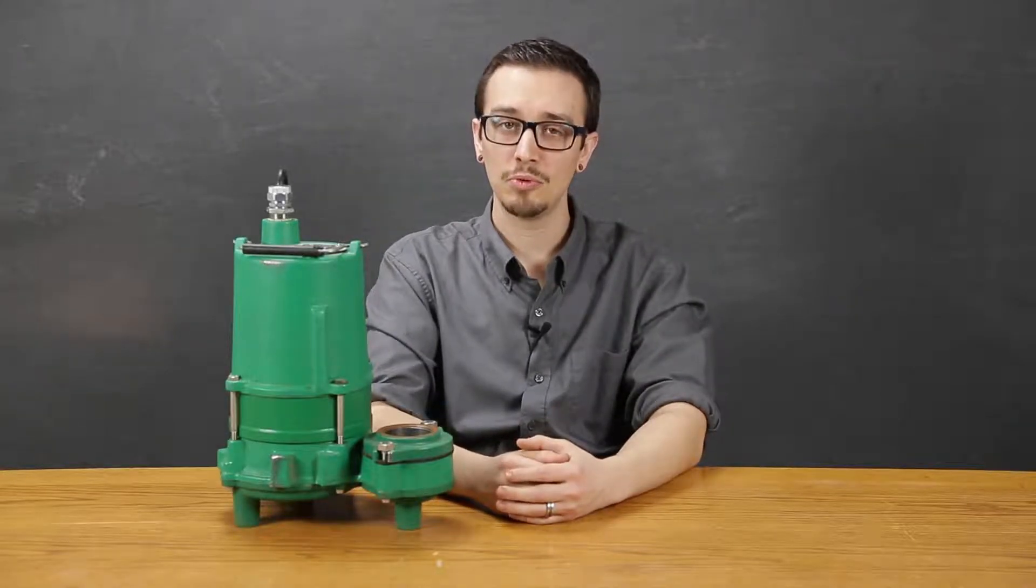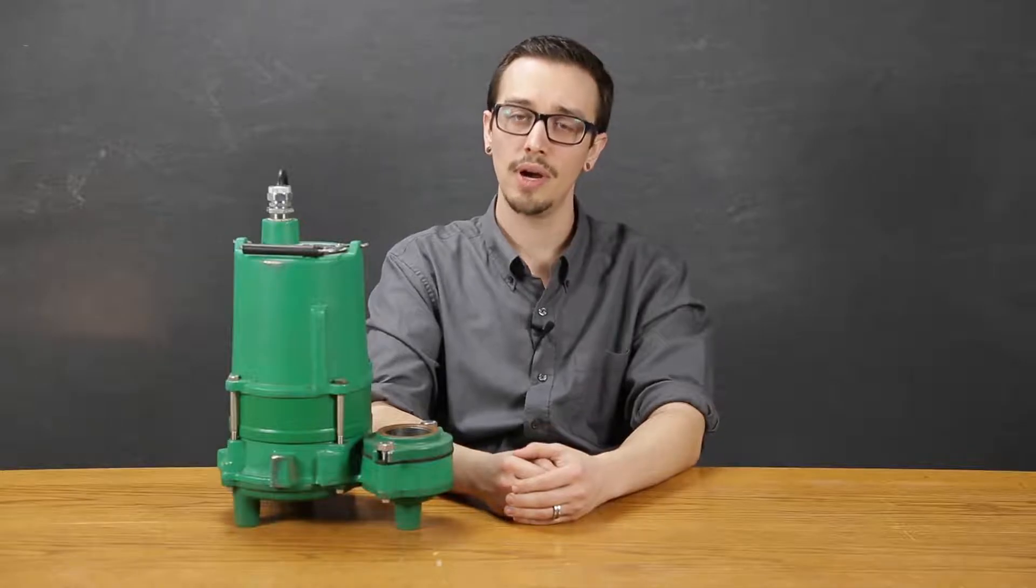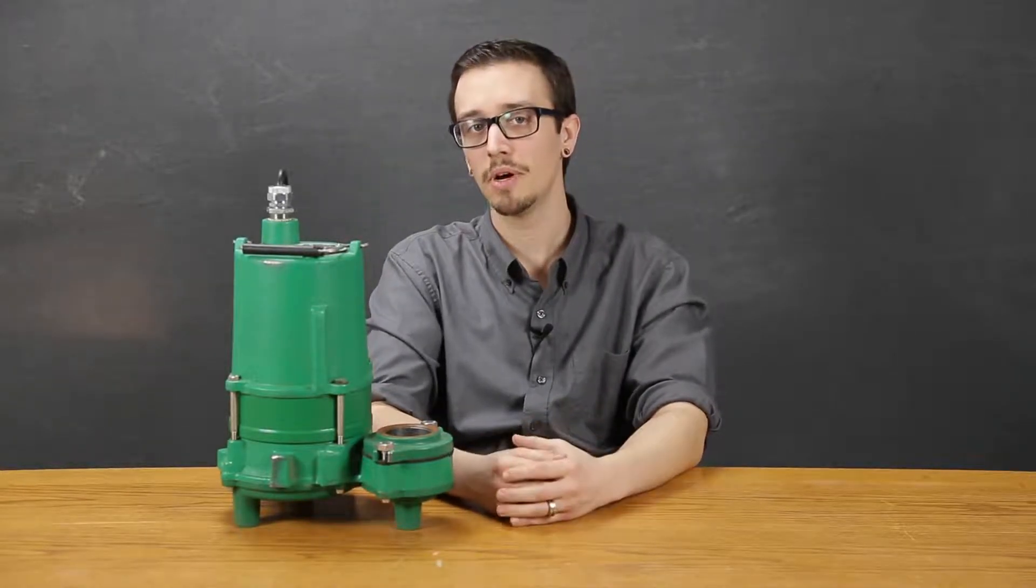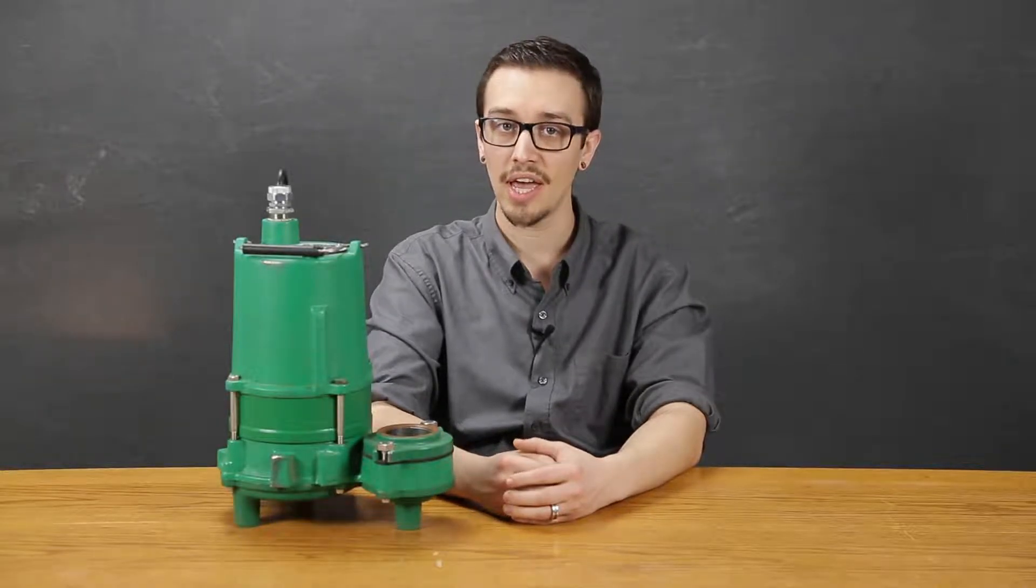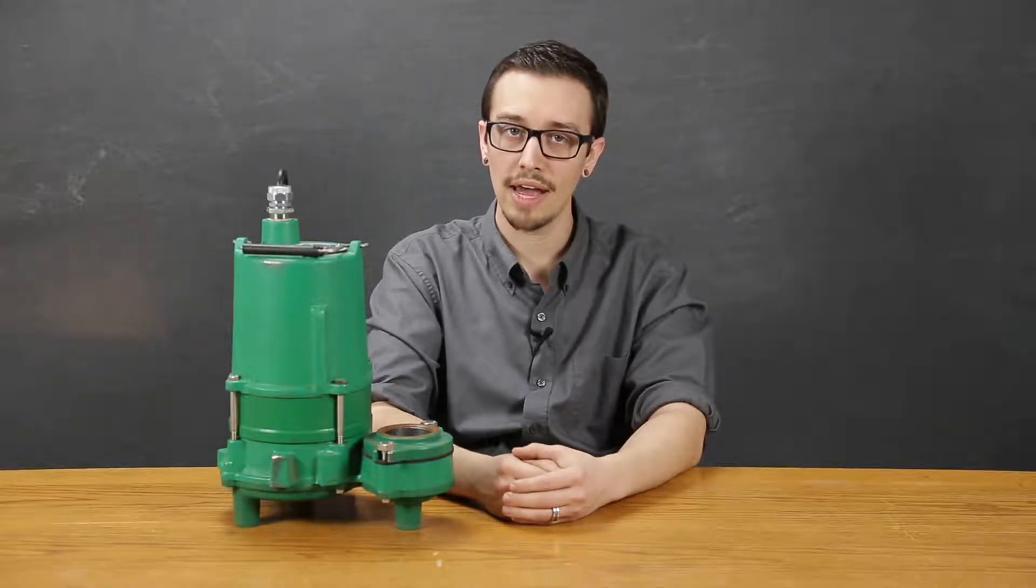The coat of paint is between 3 to 4 mils thick, which is roughly 75 to 100 microns. This pump comes standard with stainless steel hardware and features a carbon ceramic mechanical seal and the motor has single row ball bearing construction.